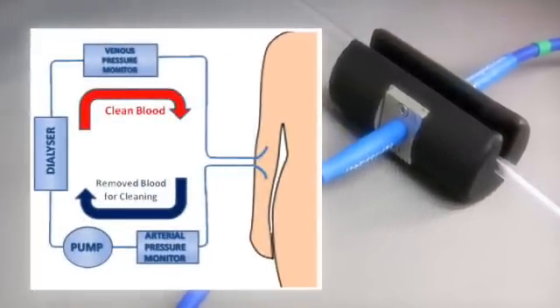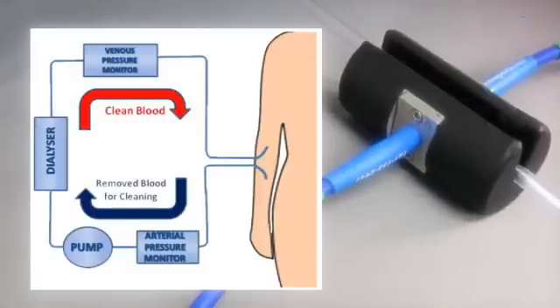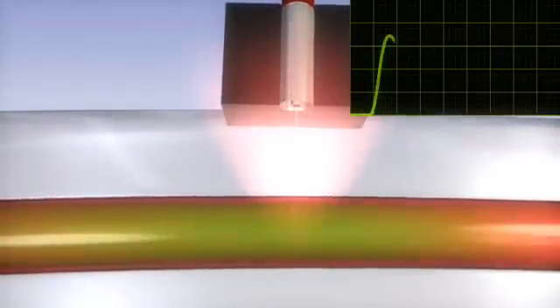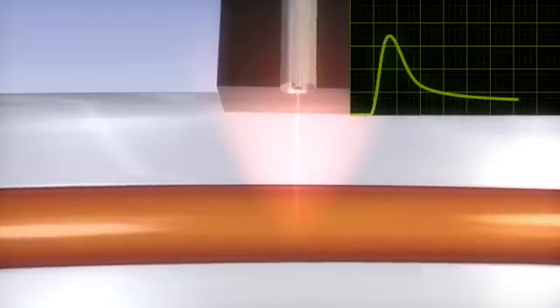The device is an optical element comprising two optical fiber cables and a receptacle for the circulation line. This device is self-calibrated using a novel patent-protected method. The dye that flows with the circulating blood is illuminated by a near-infrared light attached to the probe, causing the dye to fluoresce. The fluorescence intensity is recorded.